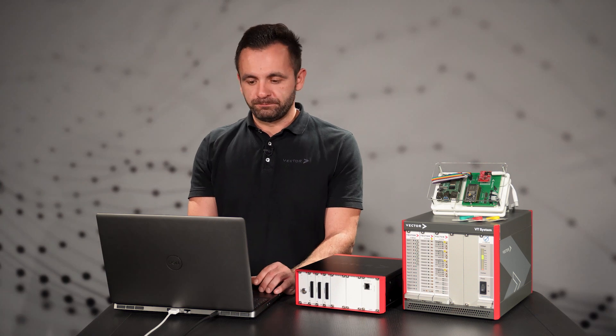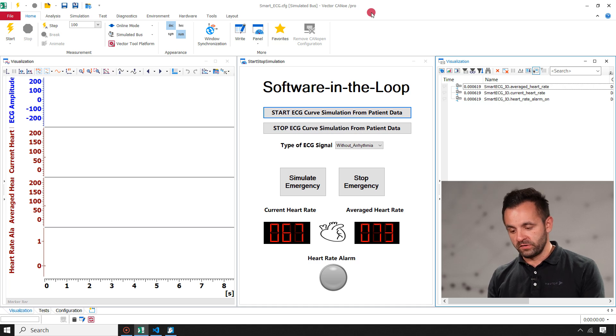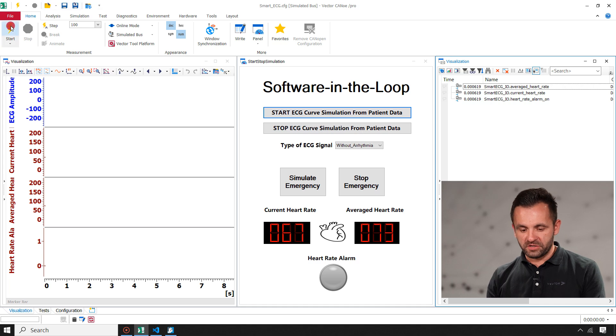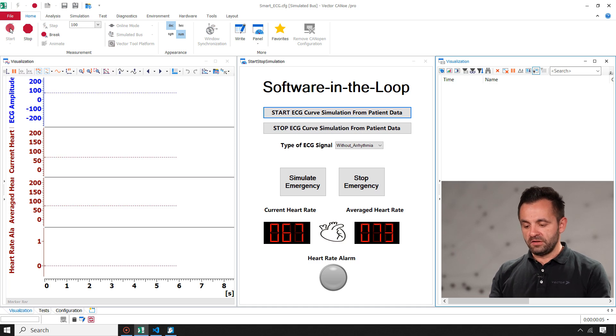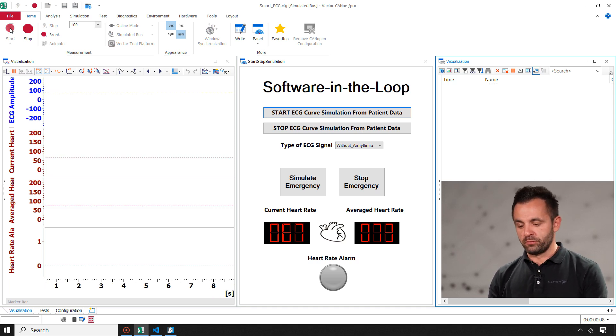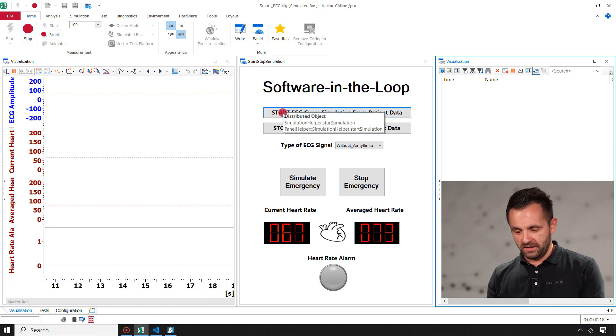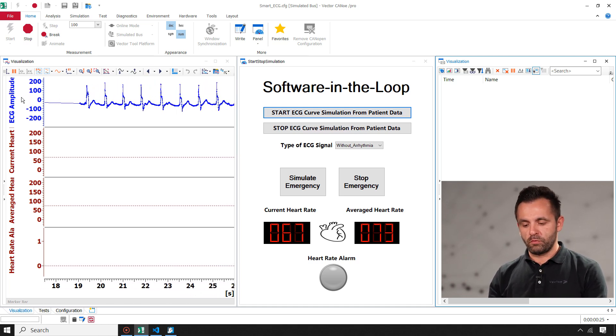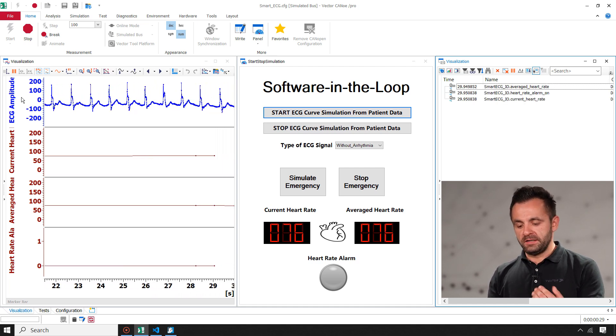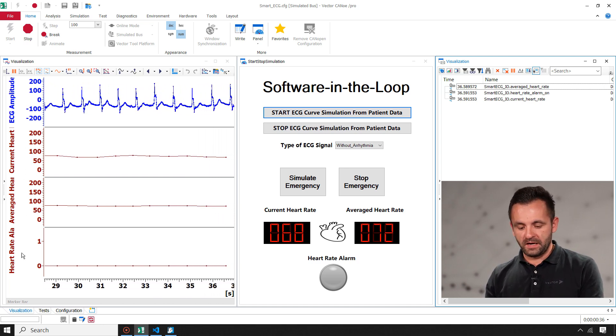Now let's start the virtual ECG device and see how we can test it with CANoe. CANoe has a highly customizable user interface, which I have customized for the special use case of our ECG device. After starting the measurement, we can start the patient ECG signal input simulation by, for example, a replay of patient data, using a MATLAB model, a Python model, or recorded patient data. Now you can see in the upper left the replay of a patient signal of a healthy patient. After some time, the SUT — the virtual ECG device — answers by sending back the current heart rate, the averaged heart rate and the heart rate alarm.